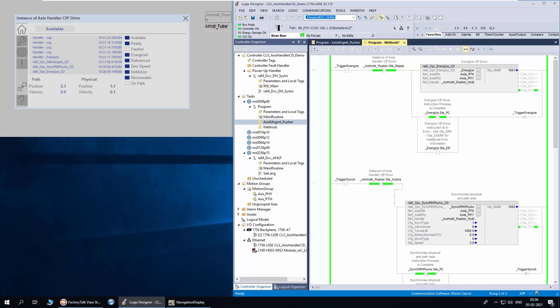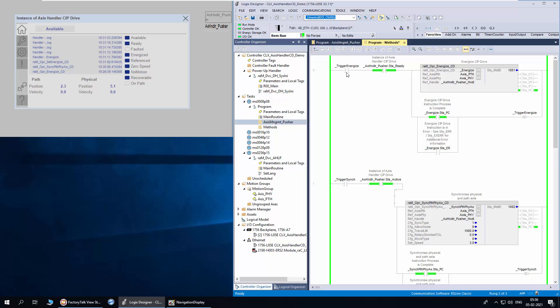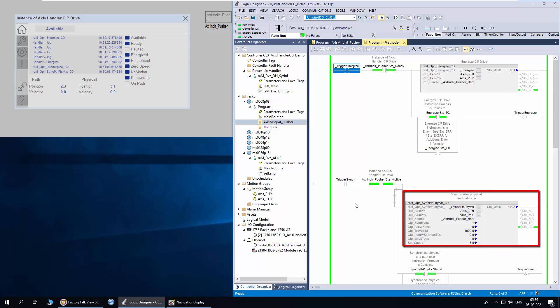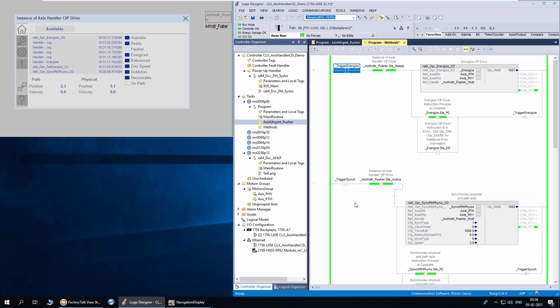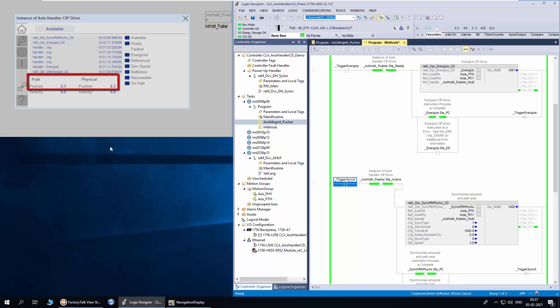I have included a few methods in this application demo to demonstrate the recovery of the physical axis to the path axis position. First, to energize the axis, I will use the energize method. I will trigger the instruction. Now the axis status is energized. The sync path physical axis method can be configured to recover the physical axis to path axis position or path axis to physical axis position. For this demo, I have configured it to recover the physical axis to path axis position. I will trigger the sync method. You can notice the physical axis is recovered to the path axis position and also geared, thus setting the on path status.